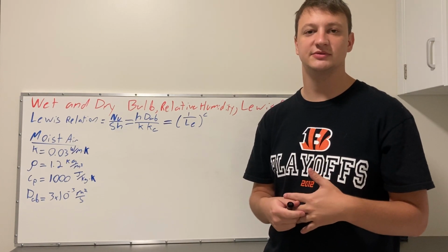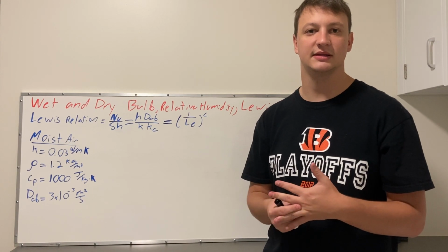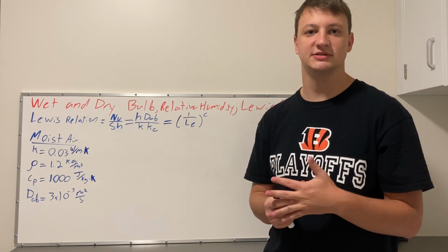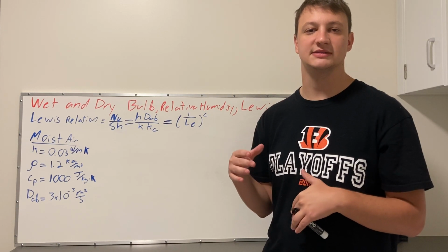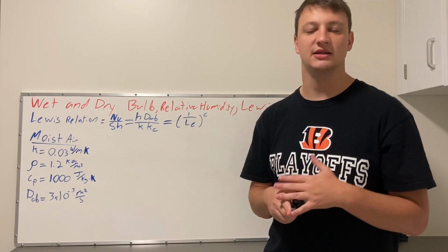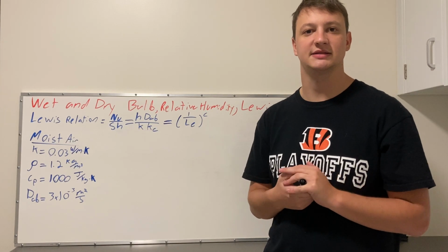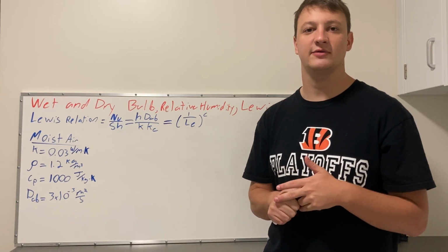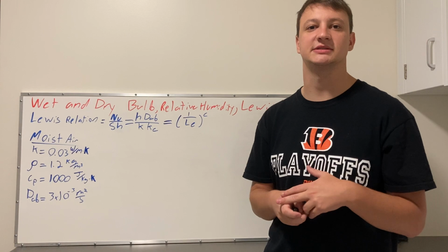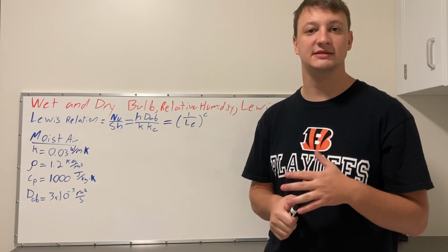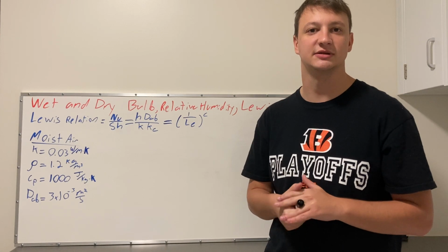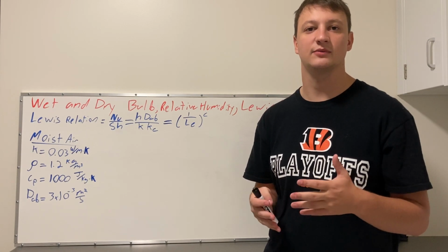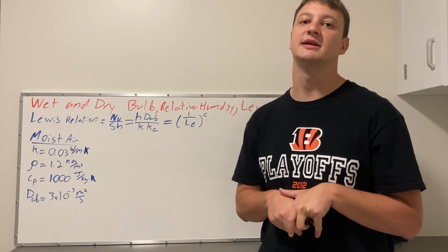With wet bulbs, you have a liquid within the thermometer to measure temperature, and as that water evaporates, it reads a lower temperature than the ambient temperature. The dry bulb, without the evaporation, reads approximately the ambient temperature, and the difference between dry and wet will give you relative humidity.